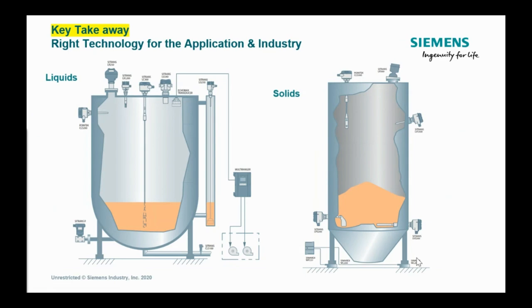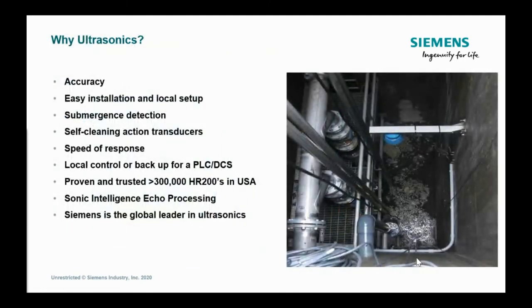All right. So since we're talking about ultrasonics, what is the key advantage? Why would we use ultrasonics to begin with? They've been around for a long time, about 40 years, you'll find. The one key thing about ultrasonics is if accuracy is your primary driver, and this is where it comes into open channel flow measurement, for example, ultrasonics are still the most accurate level technology out there. Comparing to radar, ultrasonics are typically 3 to 5 times more accurate.